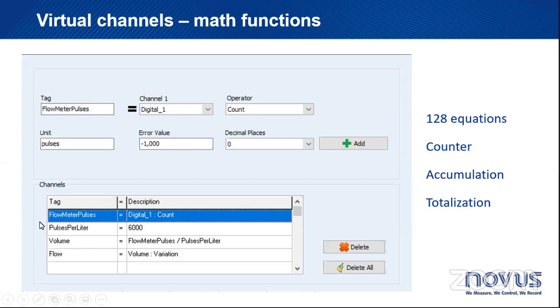Then next step, pulses per liter, I define a constant. So you go to the operator constant, you define a number, and that's it. So I used a constant of 6,000. Why 6,000? Because I want to do a division. I want to divide the pulses I'm counting by the standard of the flow meter, which is 6,000 pulses per liter. Then I can find out what the volume is.